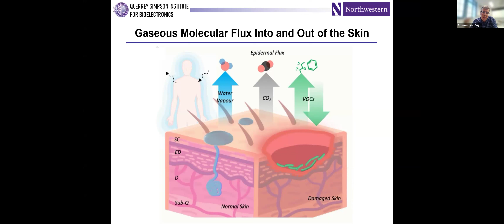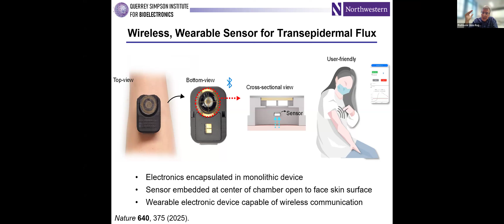And so there we've developed a slightly different device, not microfluidic. It's a device that forms a sealed chamber at the surface of the skin. Instead of having sensors in direct contact with the skin, we have sensor suites floating within that chamber. In addition, we have a programmable valve that allows us to close that chamber to the ambient or open it to the ambient. When that valve closes, we can measure the time dynamic change in concentrations of various gaseous species that emerge into that microclimate, as a way to determine quantitatively the flux of those species up through the surface of the skin. This is an exploded view cross-sectional illustration of how the device is designed: that floating sensor suite within that chamber, that microclimate, and then a bistable magnetically activated valve that allows us to open and close that chamber to the surrounding environment.